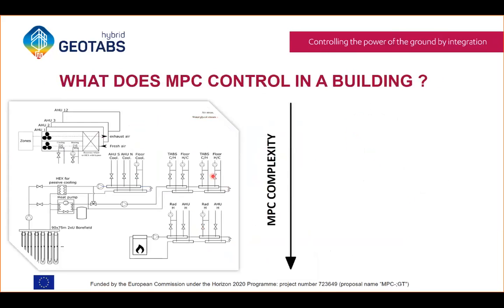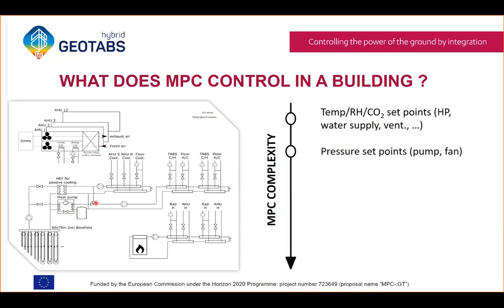That was in brief what MPC is about, but the question is, what can MPC control? That depends on its complexity. The most simple MPC will control temperature set points, for example the heat pump supply set point or ventilation set point, calculated based on the model and weather forecast, replacing a standard heating curve control. But if the model also contains pressure drop calculations, efficiency as a function of modulation, or even includes valves and dampers, the MPC can directly control these points too, though that increases model complexity.